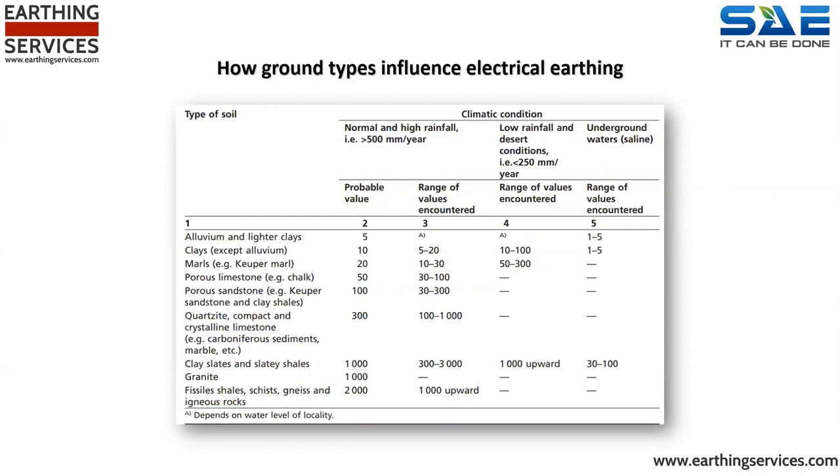Beneficial salts and moisture content of a ground mass significantly affect moisture content of a given location, which in turn largely contributes to the electrolytic soil resistivity of that ground mass. Whilst temperature affects soil resistivity, it is only in frost-type conditions where its effect is notably negative, and as such, its influential contribution is deemed to only be applicable up to the first 0.5 metre below the ground. This is a major factor why electrical earthing systems are usually installed in the ground no shallower than 0.6 of a metre, and why systems shallower than 0.5 of a metre are usually dismissed as ineffective.